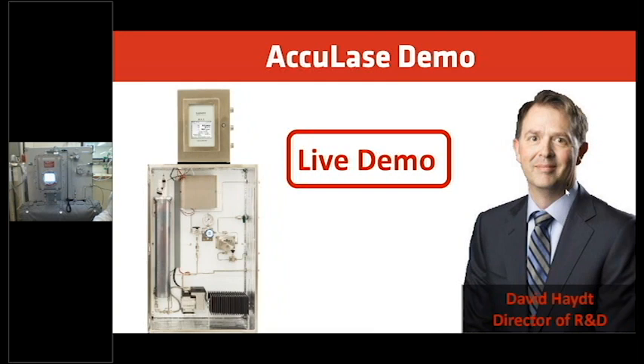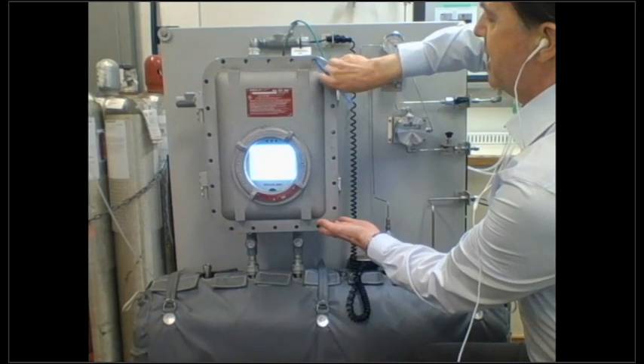We have basically 2 enclosures. The upper one contains the electronics that operate the system and has all the customer inputs and outputs. And then we have another separate enclosure that contains the laser itself, the gas cell, the vacuum pump, all the things that are required to actually make the measurement. So if we have a closer look at the upper enclosure, we can see what's inside.